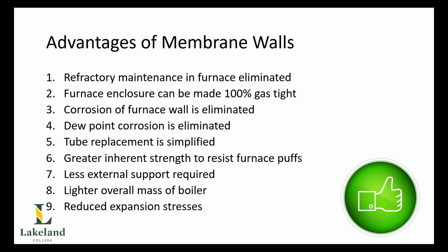6. Greater inherent strength to resist furnace puffs. A furnace puff is like a mini furnace explosion, and we'll be discussing these later in this textbook. Now, these furnaces, of course, will be designed to withstand that, as they'll be connected at the corners and tied together with something called truss rods and stays. The 7th, less external support is required. Typically, you're only going to get your buck stays and trusses around the outside of the boiler, which will give it lateral support and also allow for expansion. Because these boilers are top supported mostly, they're going to expand downwards in terms of their linear expansion.